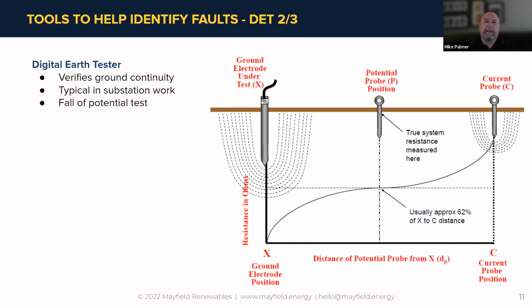So typically your electrodes, ground rods in other words, are going to be at the inverter, or you could have Ufer grounds, which are made out of concrete and steel and feed the bus bar and the inverter. But this is a fall of potential test. The center potential probe is 62% from the electrode to the current probe, which is the far one on the right. It's a real easy test. Our Getting Down to Earth booklet, this is the mainstay of it, using this fall of potential test to calculate that 25 ohms that you're going to need to acquire as per the spec for your commissioning report.